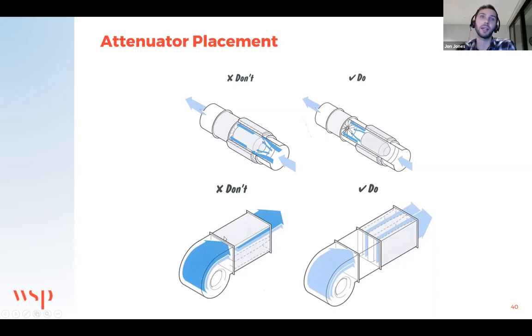Again, looking at the bottom here, there's two things to consider in this example. The centrifugal fan, if it was installed as shown on the left, you're going to get the majority of the airflow passing through the top airway only, rather than through each of the airways. So, two things to note. One, this transition section allows the air to settle down, so it does move across the full face of the attenuator.